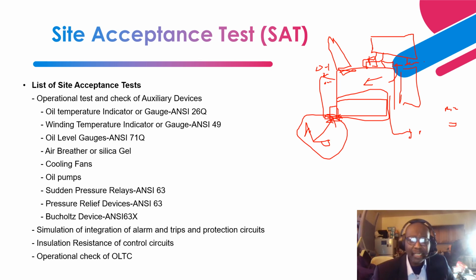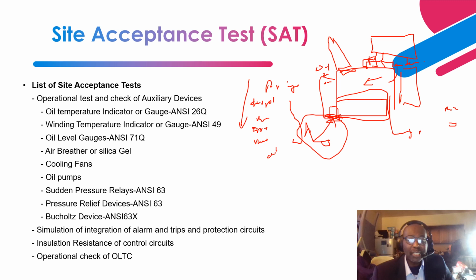Okay, so once the transformer gets there, remember, I told you all the components that are removed are packaged nicely, basically to prevent damage. Once it gets there, you as the discipline engineer, maintenance engineer, operational engineer, maintenance technician, operational technician, project engineer, project manager, it is your job to take a look at all these shipping pieces. They'll all be listed for you to check these components to make sure there is no damage to them, and that all the nameplate data or anything imprinted matches the design.